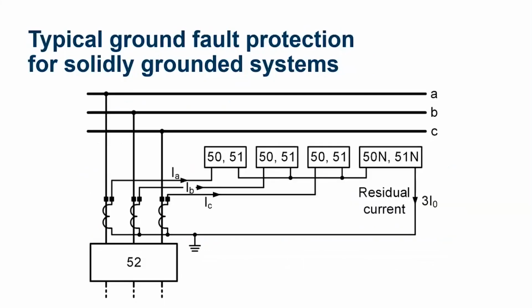And the main challenge there is that traditionally, we're going to use that zero sequence current for our fault pickup. This is going to be the current we use to operate our ground fault protection in most traditional protection schemes. And so if I have a situation where introducing a high impedance fault has the potential to reduce this current that I'm using for my fault pickup, then there's really no way I'm going to be able to detect those high impedance faults using these traditional zero sequence based 50-51 elements, this traditional protection.